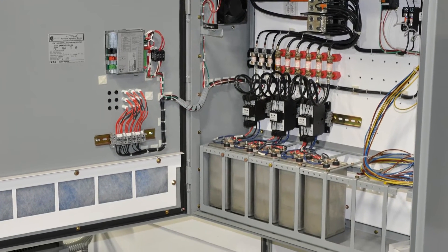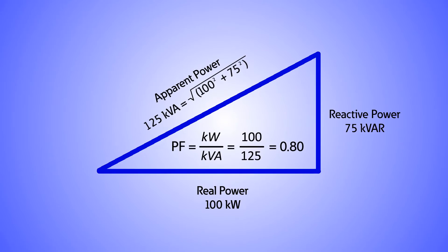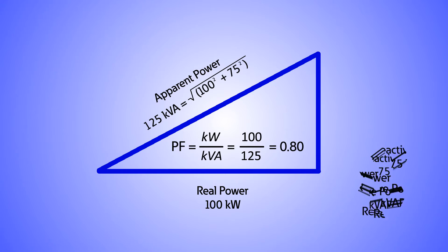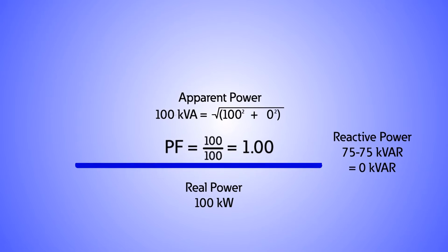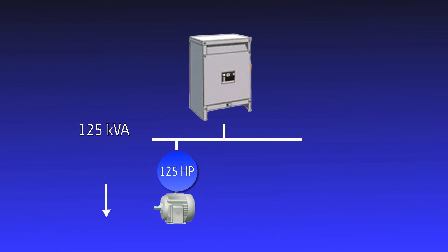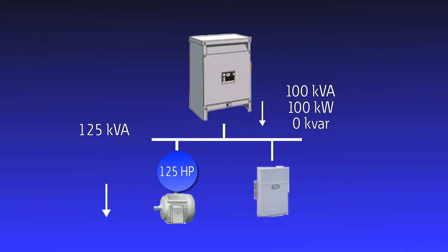Capacitors draw reactive power that is equal and opposite to the reactive power drawn by inductive loads. Going back to the power triangle, if we reduce or eliminate the reactive power required by inductive loads, our power factor will be perfect or unity. This is because our KVA would consist of only real power. Therefore, the net effect of applying capacitors is that the only reactive power the generating source has to provide is the difference — in a perfect situation, this would be zero, and the source only has to provide real power.